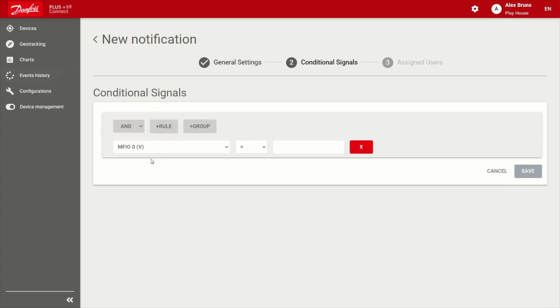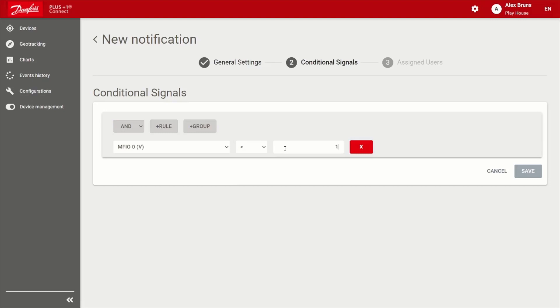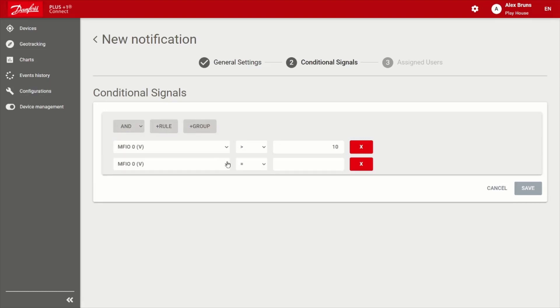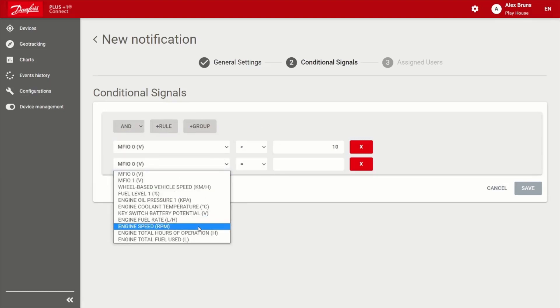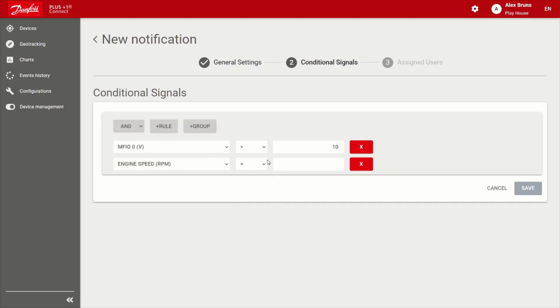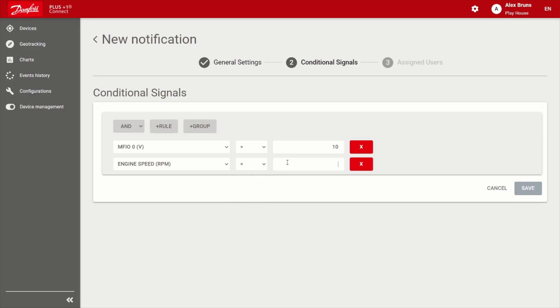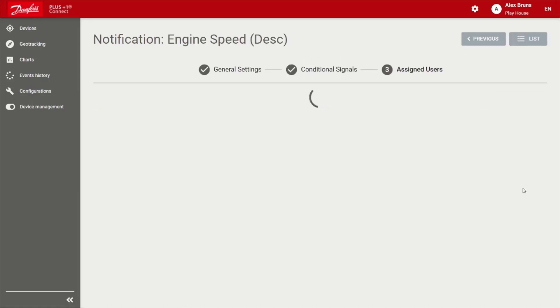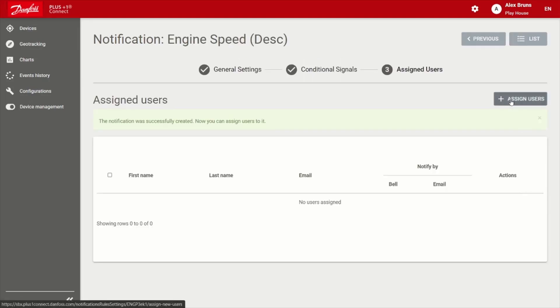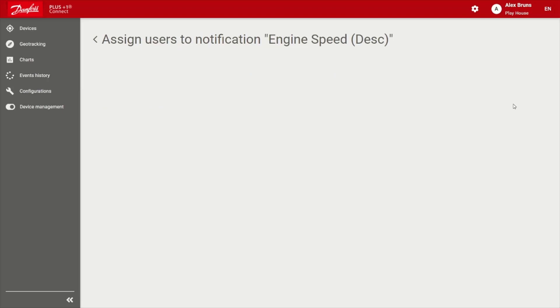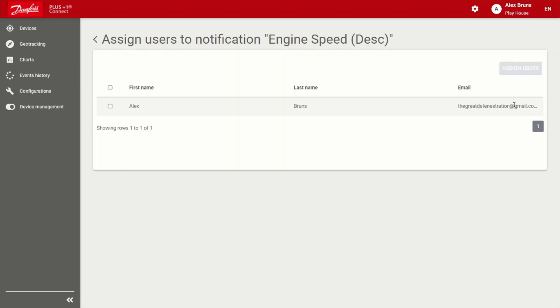All right, so we'll create that rule. So first of all, we'll go ahead and use that multi-function input. Let's say if the multi-function input is greater than 10, and we can combine this with an or, we'll go ahead and leave it as an and. And I did mention engine RPM, so there we go. So multi-function is greater than 10, and engine RPM is less than 1800, I shall get a notification. So we go ahead and save. I'm going to go ahead and assign myself to this notification.